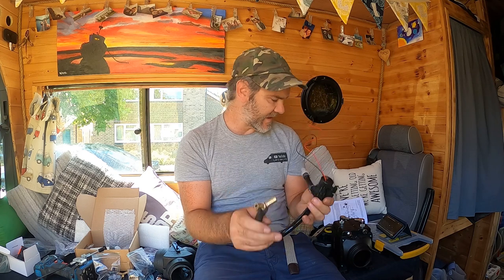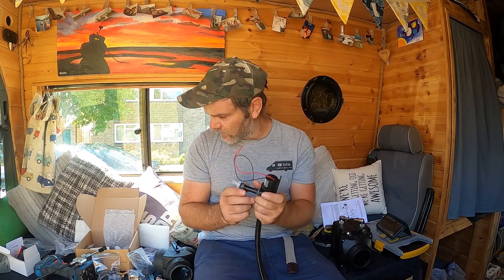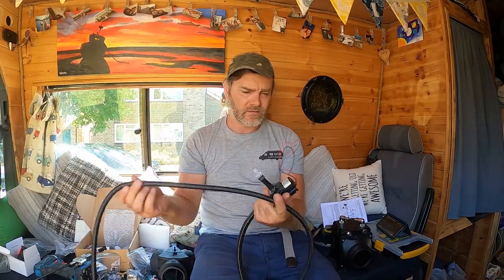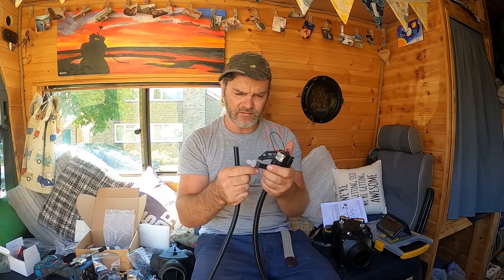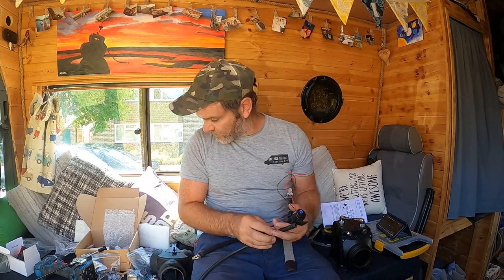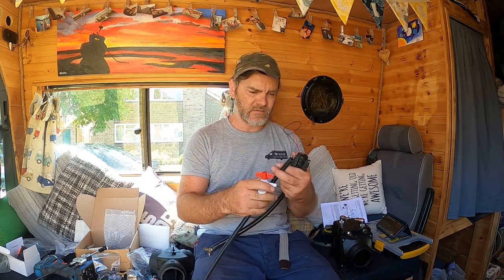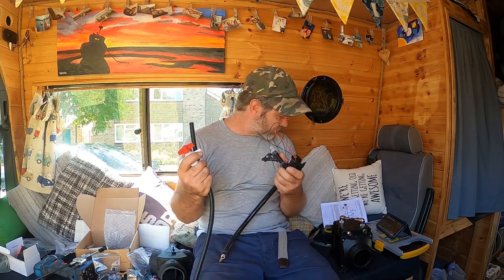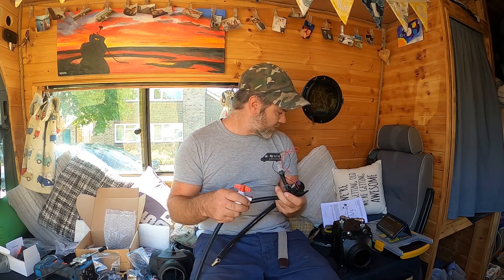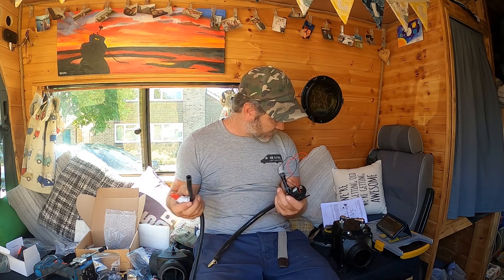I know where this is being mounted — I'll fix that in a minute. This side goes to an isolator valve and a little section of hose which they say can act as a bit of an accumulator, so you don't need a separate accumulator for this system. I need an isolator valve so I can switch off the circuit of this pump. Then it splits into a T and goes off to the cold tap, a drain valve, and if you've got a shower as well.